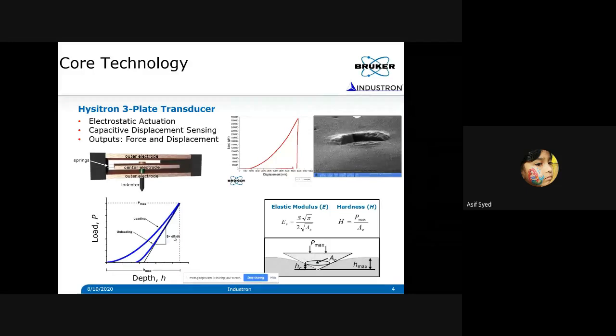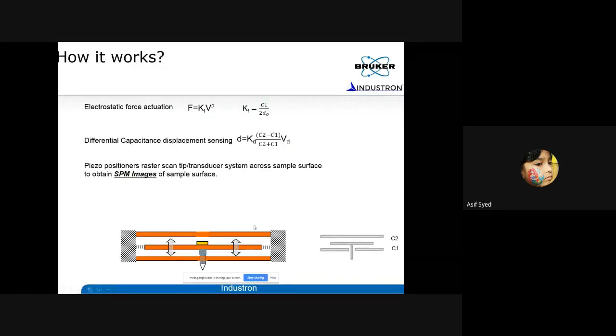Okay, so in the next slide I'm going to show how the force is generated, and how it is applied onto the sample. Electrostatic force means you apply a high voltage between the central electrode and the bottom electrode, and the force is basically voltage squared times a constant. So this is a very simple equation, and you can calculate the force if you know the voltage you applied. So the force determination is pretty easy.